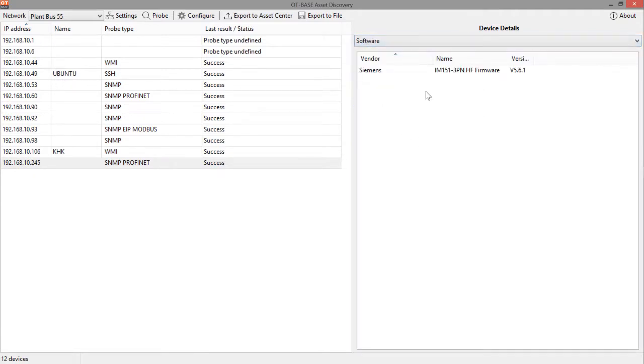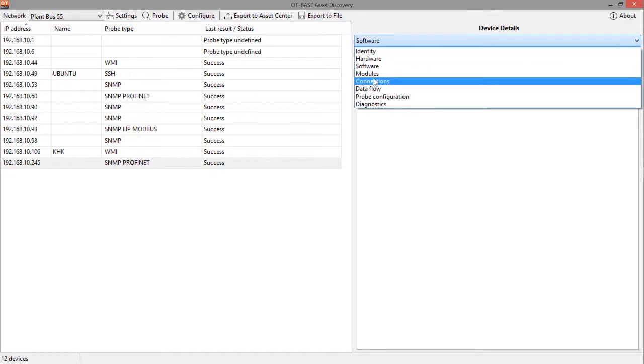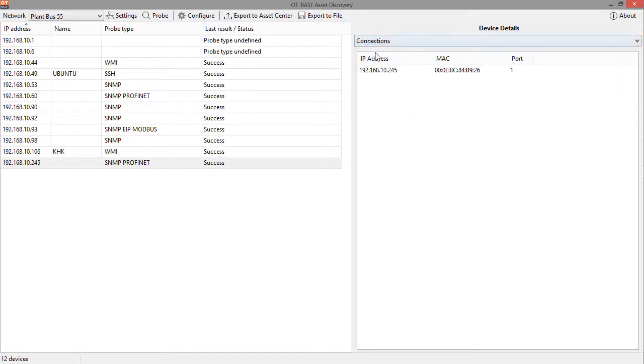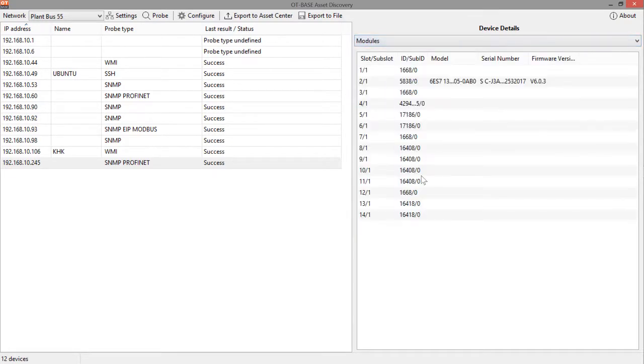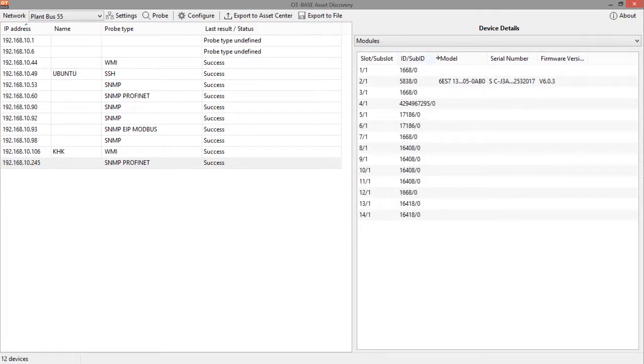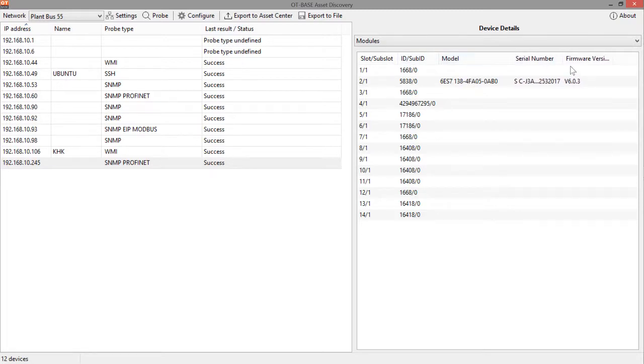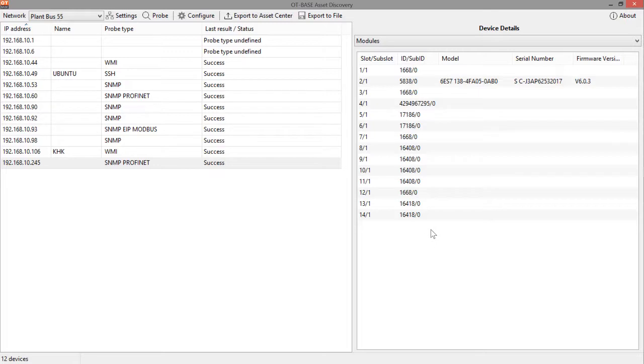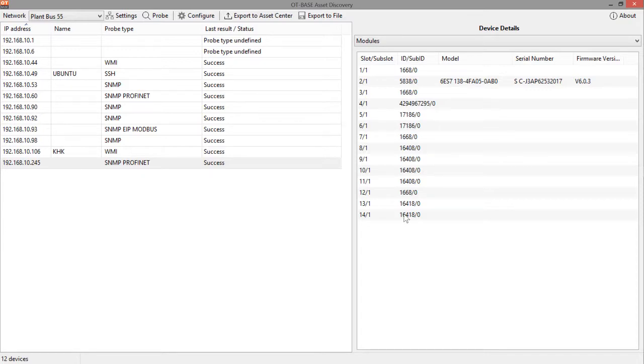Let's move to software. It shows us the firmware version. Then you see any I/O modules that are installed in this RTU. And by the way, what you see here is just the reference IDs of the hardware products. And once this data is sent to the OT-BASE Asset Center, it will be translated to human readable text. But asset discovery only shows you the IDs, the numerical IDs. So don't be surprised about that.